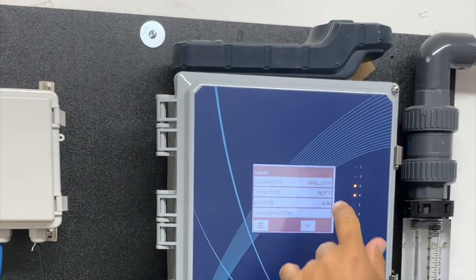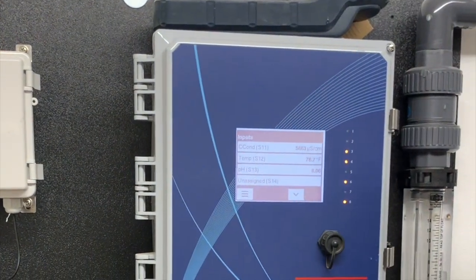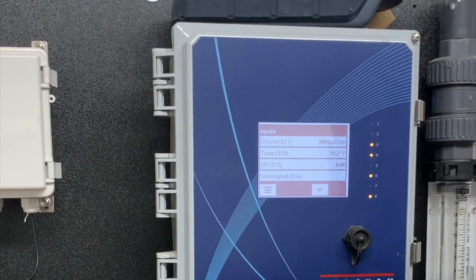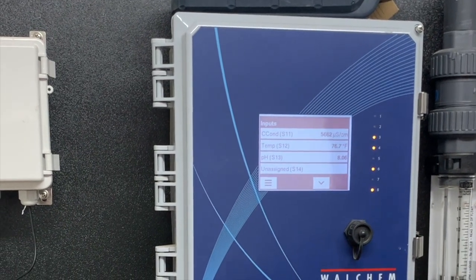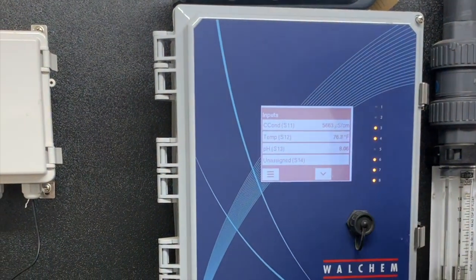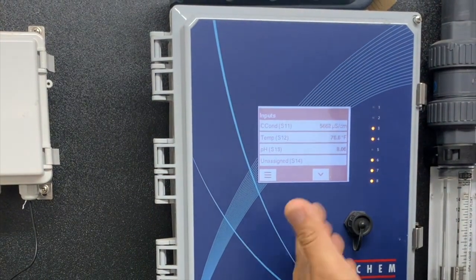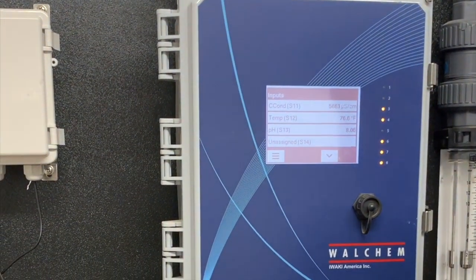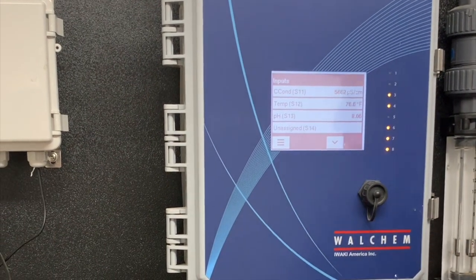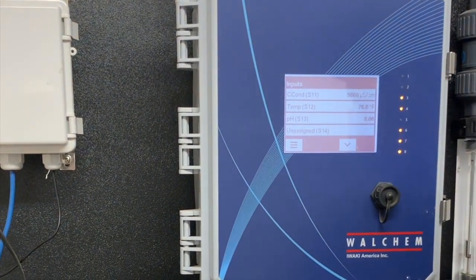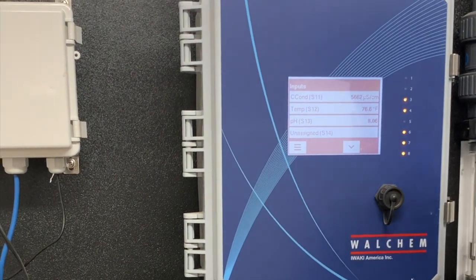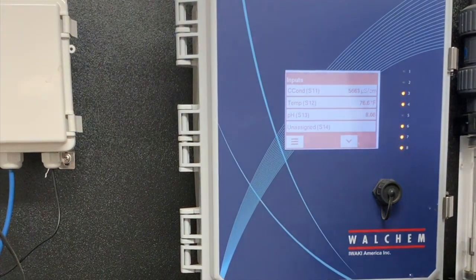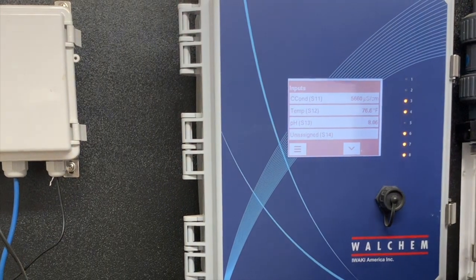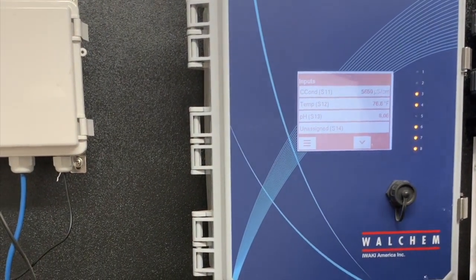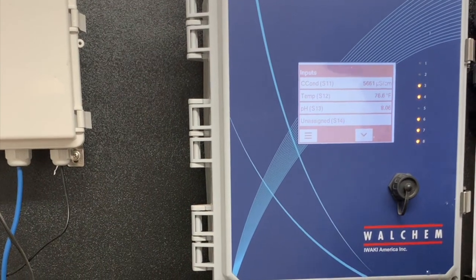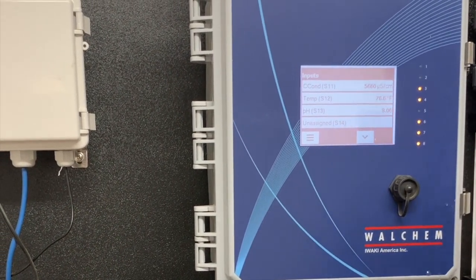Now, if our reading didn't take in our calibration and for some reason we put our calibration in and it was off and it wouldn't save the calibration, it could be a couple things. Maybe your probe's still dirty, maybe your probe is not connected properly, so I would check the wiring connections, or possibly your probe is just no good anymore. In the conductivity probe, there is other troubleshooting we could do across it to check it. On your pH or ORP, after about a year, usually your probes start to fault. So we would probably go ahead and change those probes out, the actual electrode part of it. So that's pretty much it.